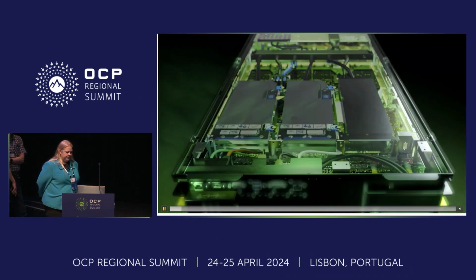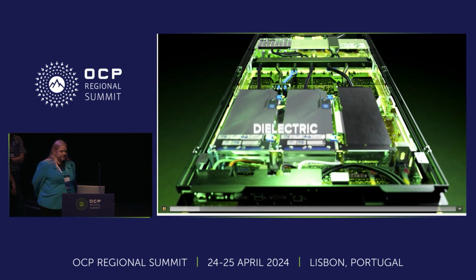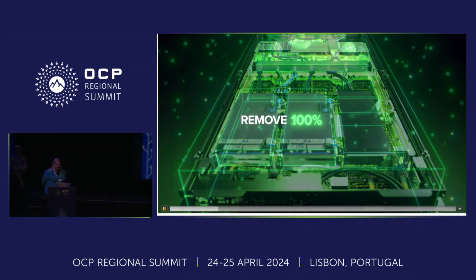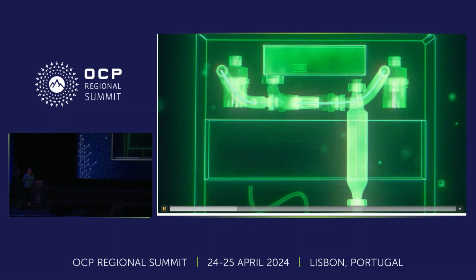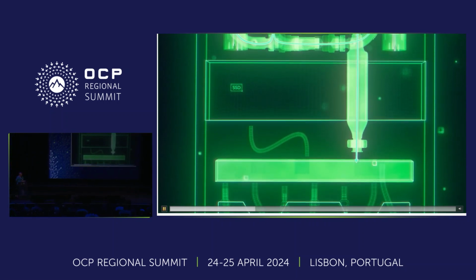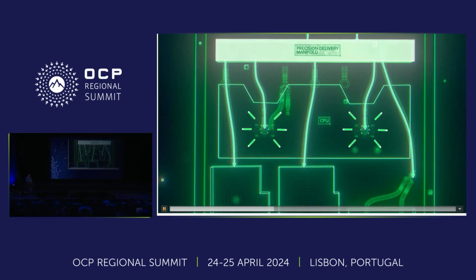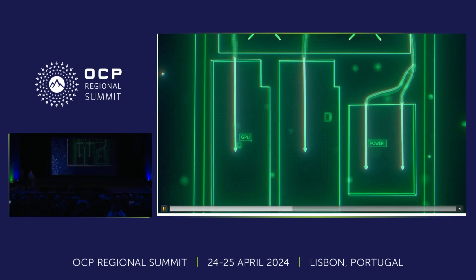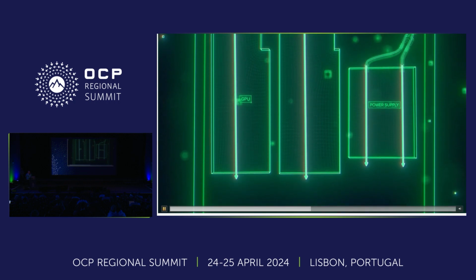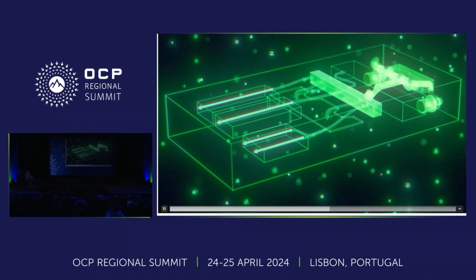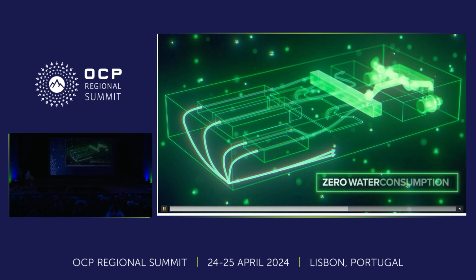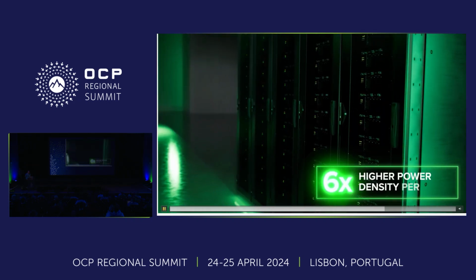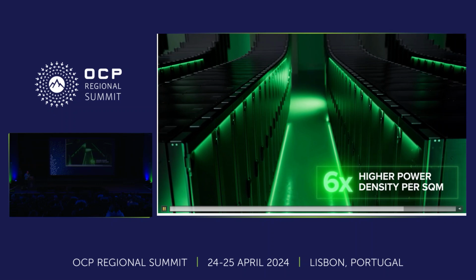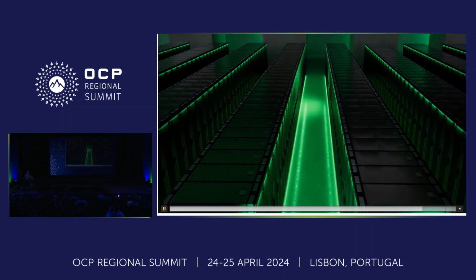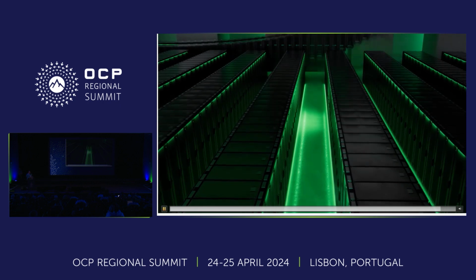A small quantity of environmentally safe dielectric coolant is precisely targeted to remove nearly 100% of the heat from the hottest components of the server through an in-chassis manifold. The coolant runs in parallel to the CPUs, GPUs, power supply, and SSDs simultaneously for maximum efficiency and reliability. Heat can be rejected to dry coolers or captured and reused for heating, negating the need for evaporative cooling and water consumption. We enable you to scale up from a single server to multiple racks within your existing air-cooled architecture, freeing up stranded capacity and offering more flexibility within current white space.